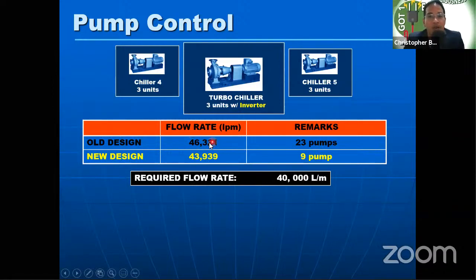With the old design, we had a flow rate of 46,321, using 23 pumps at that time. But with the new design, since we installed the turbo chillers, we also installed new chilled water pumps on the main piping with inverters. We didn't replace the ones on chiller 4 and chiller 5 since they run in base load. Remember this always: not all pumps and fans need VFDs. If your pump or fan runs at 100%, you don't need VFDs.